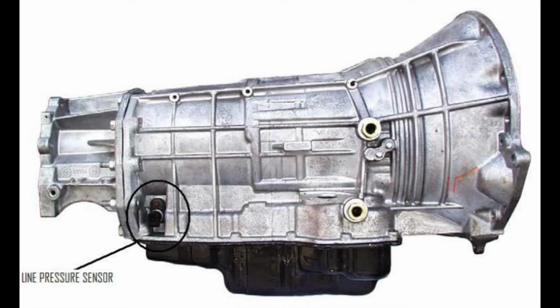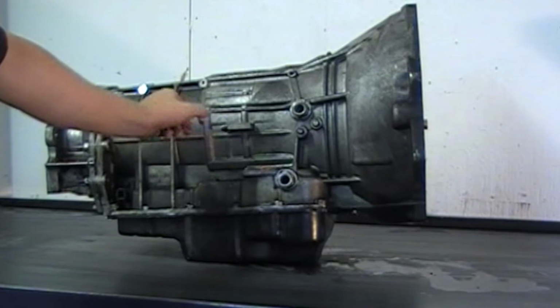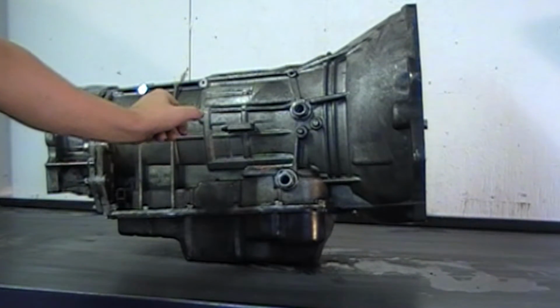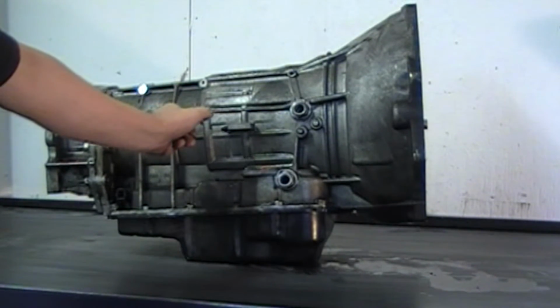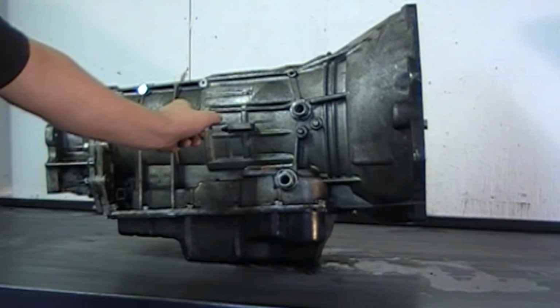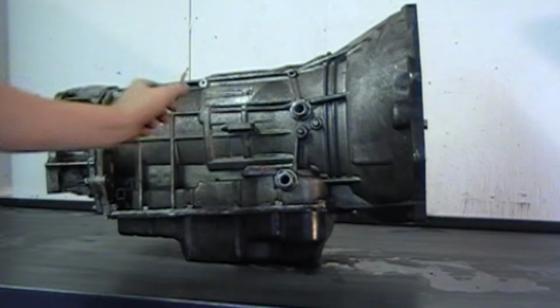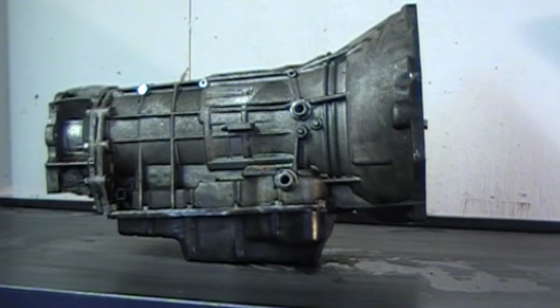Sometimes, being that these units have been hot and cold so often, that O-ring will seat itself and it may take a little bit of finesse to get them out. Don't pound or tap on them, just kind of a gentle twist side to side, and then just straight forceful pulling, and they should come right out. If you smack them or give them a tap, more than likely you'll break them right off, and then you'll have a real difficult time getting them out.